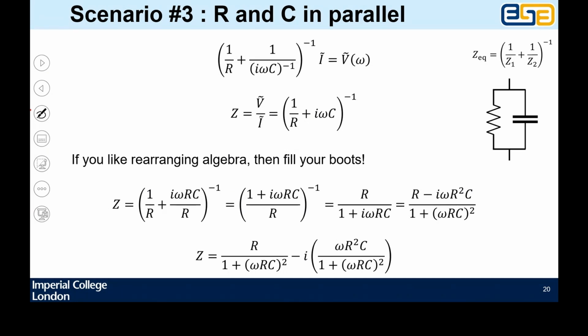Small is a relative term, so you need to define a little v naught based on what you're looking at. If you are looking at an electrochemical system, I could put Ivan on the spot: how big's your stimulating voltage when you do EIS normally? I use 5 millivolts usually. Yeah, so in the millivolt range. But people do impedance of compressed soil stacks or concrete blocks, and I bet they're using a much bigger stimulating voltage there. Otherwise, they won't get any signal out the other side at all.